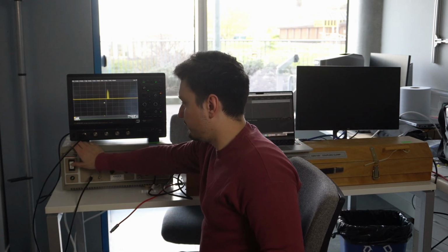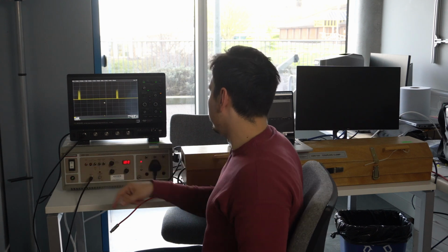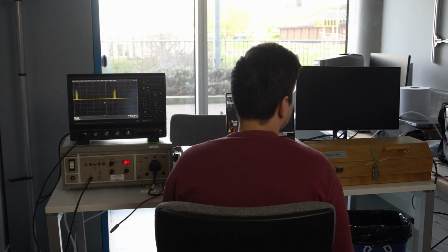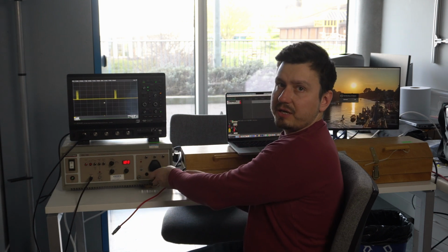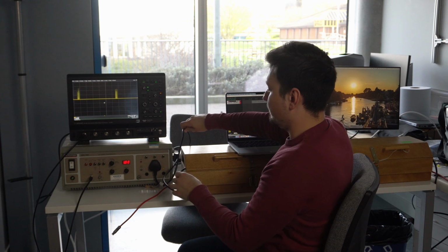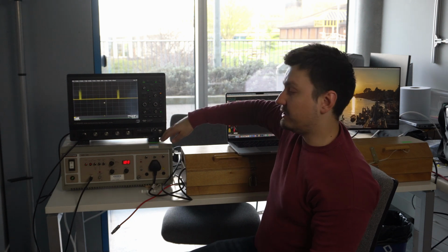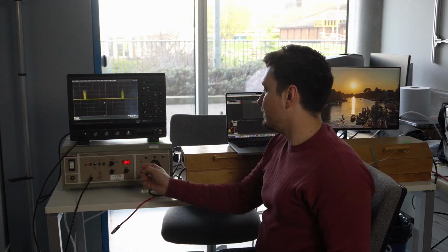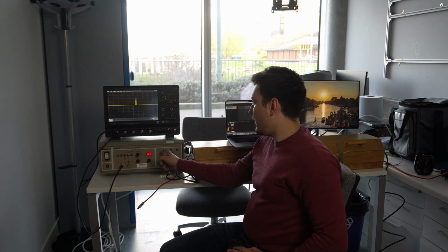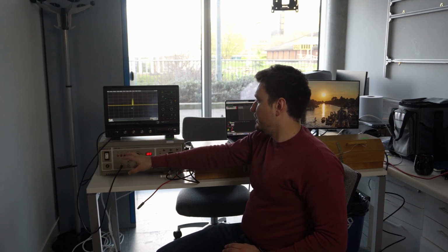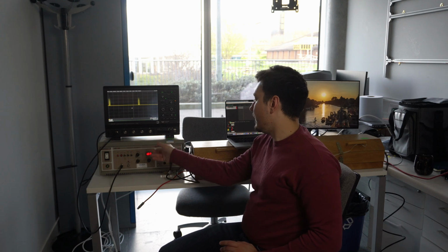The first thing you have to do is switch the power on for the display that we're going to test. What's happening here is that this display is powered from the NSG1025 transient generator. This is how it's able to apply the transients into the mains supply. Now, you have several options here. You can see that even though everything is aimed and ready to fire, I'm not actually applying any transients into the power outlet yet.